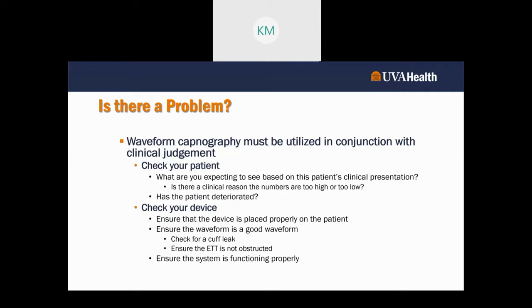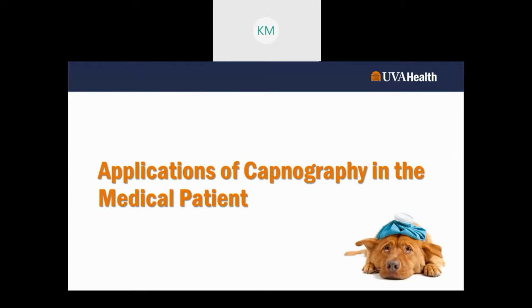Ensure your device is properly placed on the patient, that you have a good waveform, and that the waveform is what you expect. A patient with a broken leg should have a normal boxy waveform, but a patient with COPD or asthma may show the shark fin waveform. Think about what you're expecting to see and whether you're seeing it, and ensure the system is functioning properly.